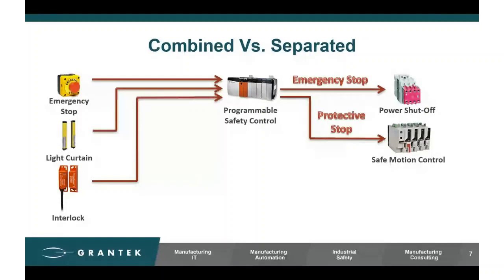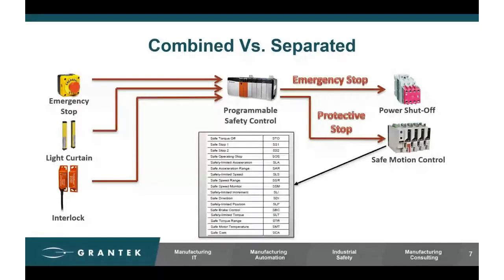What if we took it one step further and took advantage of safe motion technologies, which can do a bunch of things instead of just removing power or even pausing the machine? Safe motion technologies today follow IEC 61800-5-2, which spells out how to do over a dozen or so different safe motion capabilities. For example, safe operating speed, safe acceleration, safe torque, safe direction, safe range, you name it.